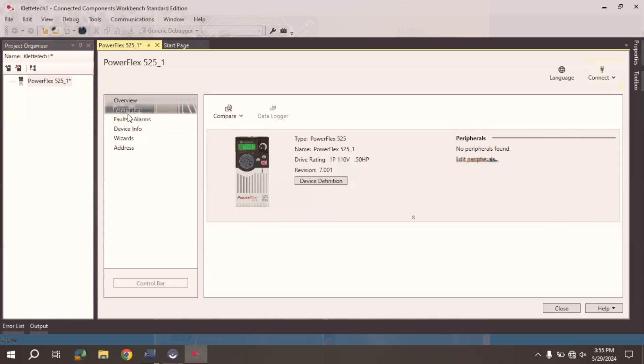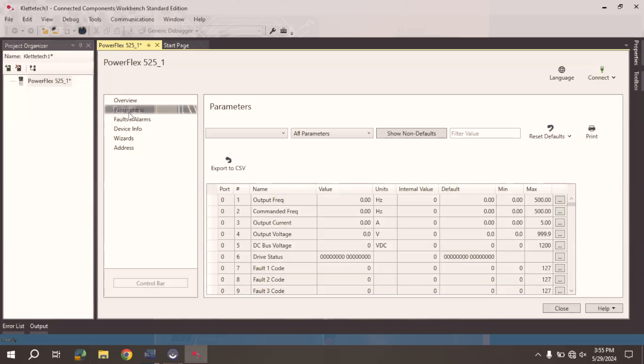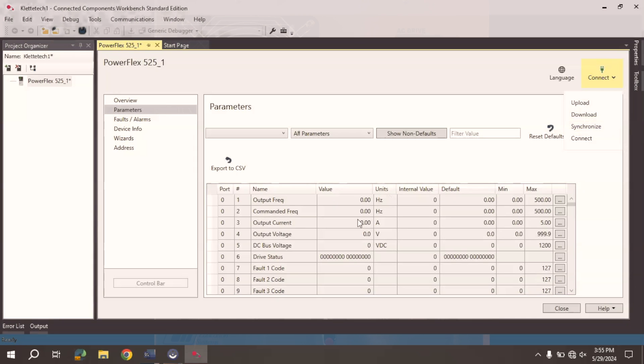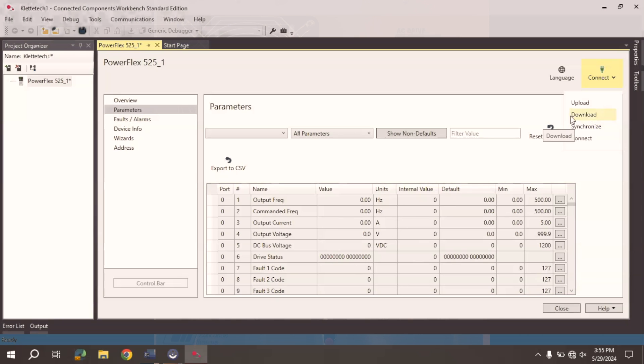Now I am actually, they are aware of each other. The laptop is aware that there is a VFD out there with a specific IP address that it can be programmed to. And I'm going to have videos on how to do a lot of this, but we can go in here to the parameters, and we can begin to either change them and download to it by coming over here to connect. I can make a bunch of adjustments in here on specific parameters, and then download to it. I can upload from the VFD, meaning I would take all the parameters from the VFD and bring them into this file.